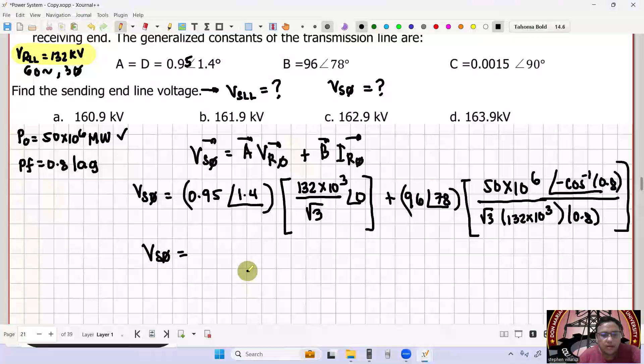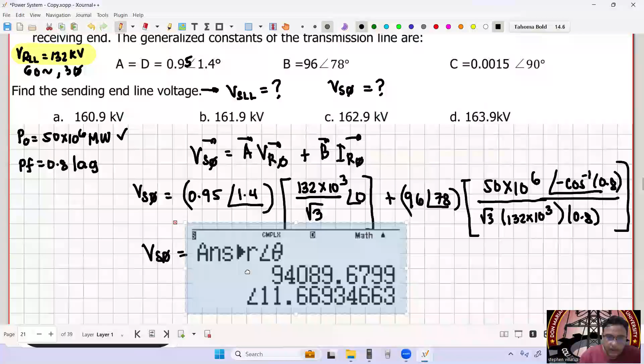So therefore, ano na yung VS per phase? Ito ay 0.95 bar angle 1.4 multiplied by 132 kilo over square root of 3, plus 96 bar angle 78 multiplied by 50 mega over square root of 3 times 132 times 10 raised to 3 times 0.8, bar angle negative arccos of 0.8. So sa polar form, ito ay equal to 94,089.67 bar angle 11.66.